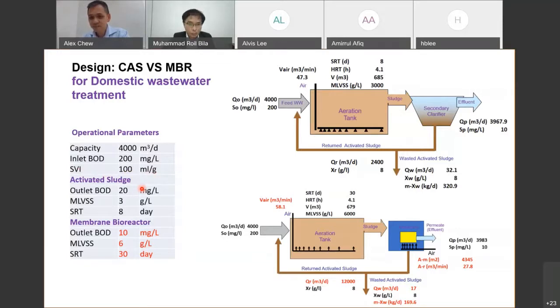So based on the operational data that I showed previously, I will have an outlet BOD of about 20. I will have a sludge concentration of about 3 grams per liter, and the sludge age is about 8 days. For MBR, I also take it from the previous slide. So outlet BOD is lower, it's 10. MLVSS is higher, 6 grams per liter, and sludge age is 30 days.